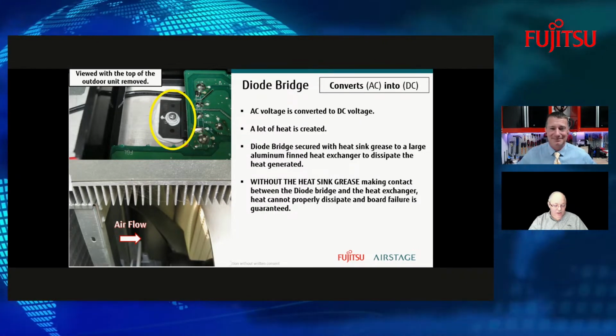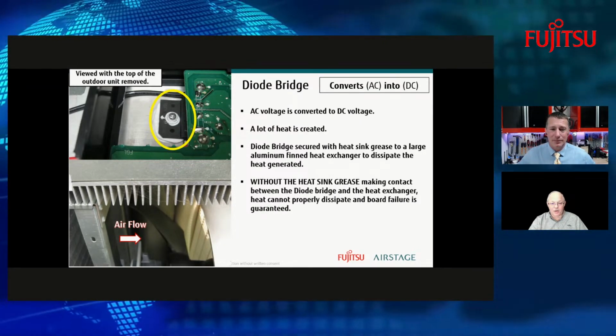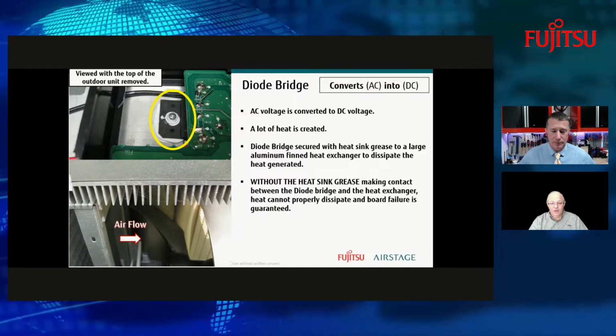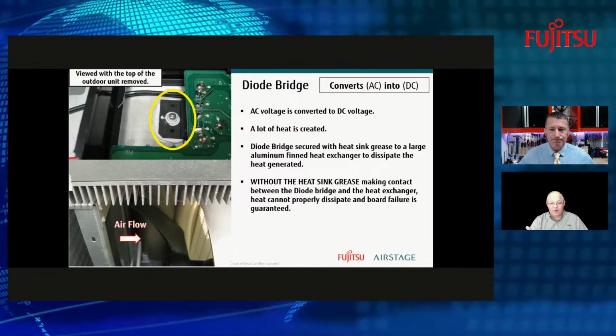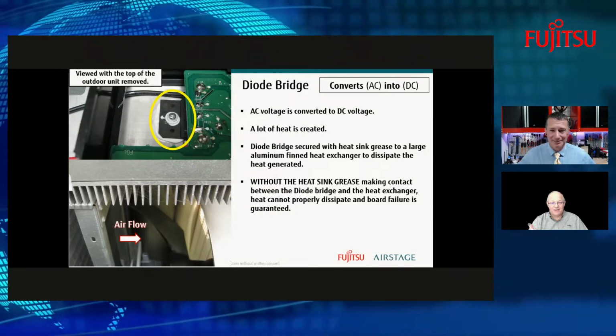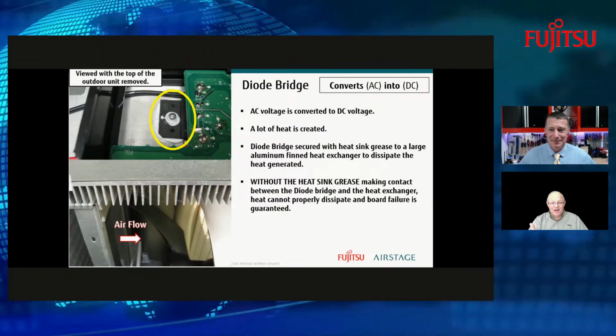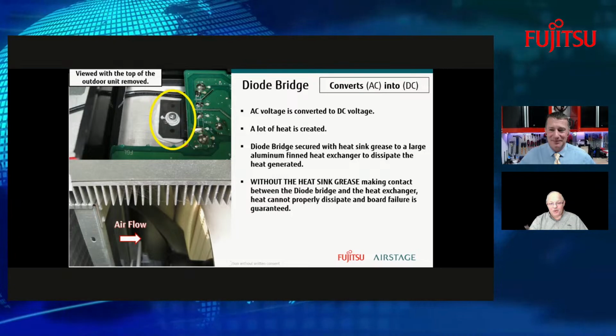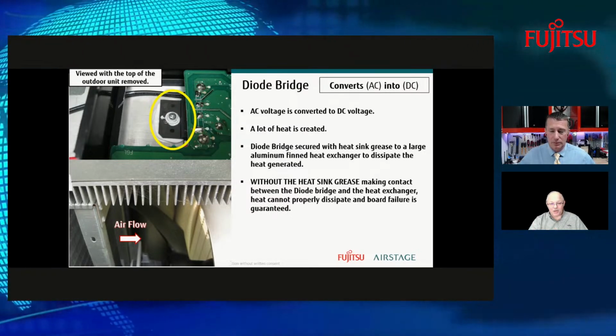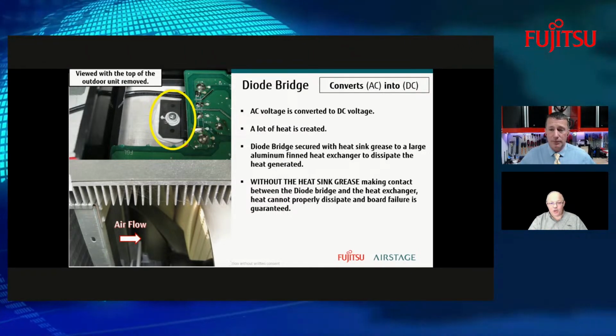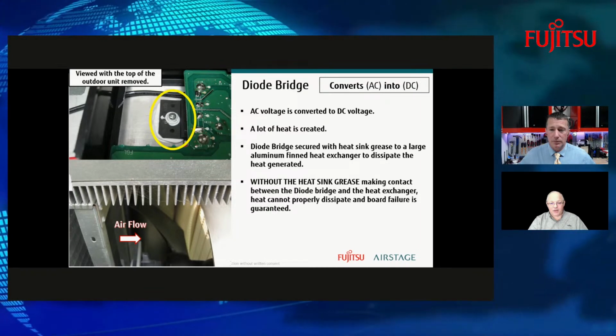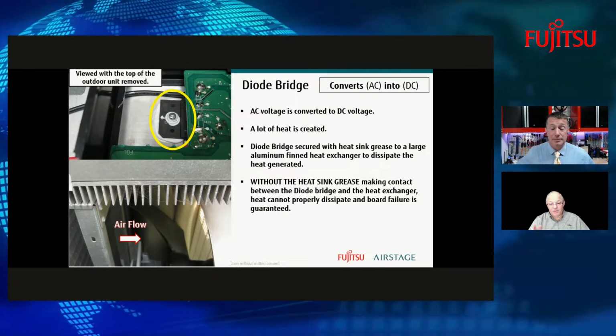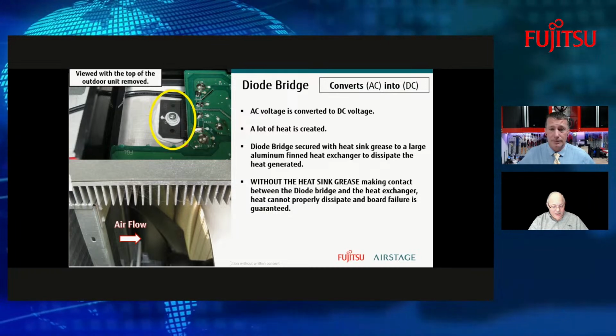That's correct. And if you look at the picture toward the bottom, you can see where the air is coming through from the blade. Well, right above that, you can see some spider webs. Right. So it's not a bad idea, at least annually, to blow that out and make sure you don't have a lot of dust accumulating underneath that heat sink, because over time you could get some things that could act as an insulator.